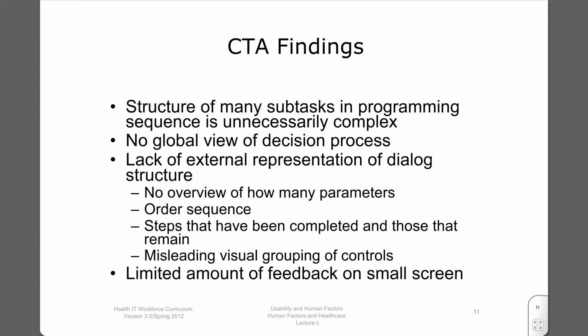There was a lack of external representations to guide the user. For example, a nurse would not know that he or she was on the third of 5 screens and was halfway through the task. The grouping of the controls was very confusing, with some buttons serving 2 functions. In addition, the screen was rather small, which limited the kind of feedback that was possible.